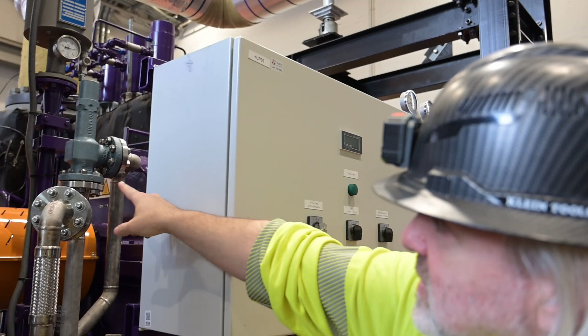Now, trip simulation interrupts the trip valve control. So by going to trip simulation, this will cause the trip valve to close, then open. This is just a one-shot. Holding it will not hold it closed. Letting go will not do anything. So you initiate, it does the test. When you're doing the test, the trip valve will close. When the trip valve closes, you can see the stem on the trip valve go in and then come back out.